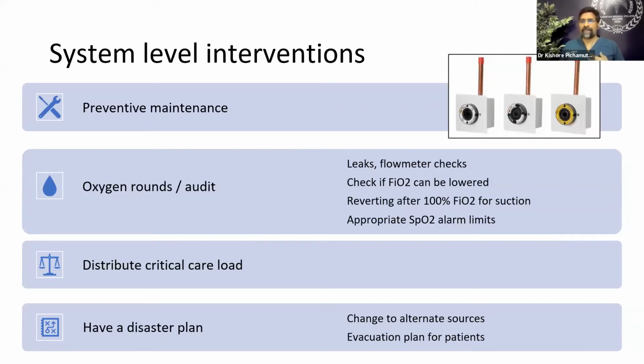And when we set conservative saturation targets, it may not be implemented at the ground level, and sometimes it helps to set a high SpO2 alarm such that it alarms when the SpO2 goes too high, and that makes everybody aware and bring down the FiO2 as well. Other things, of course, is that ICUs are, as was mentioned, very large consumers of oxygen. So make sure that the ICU loads are not on one system. Preferably, split the supply to ICUs so that all the ICUs are not on one system, overloading that oxygen supply system.